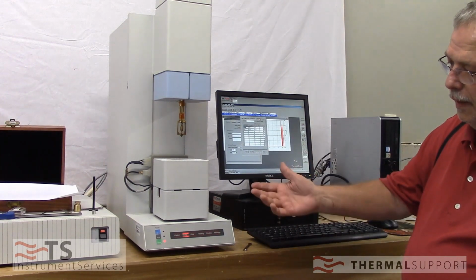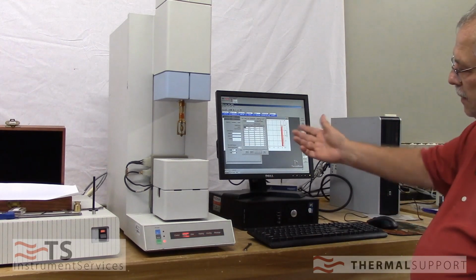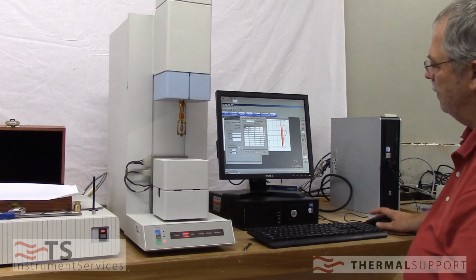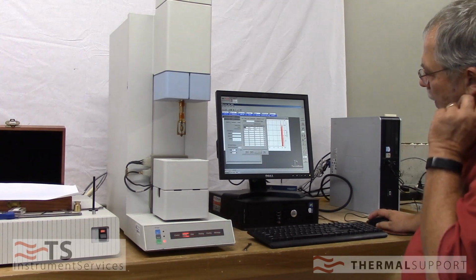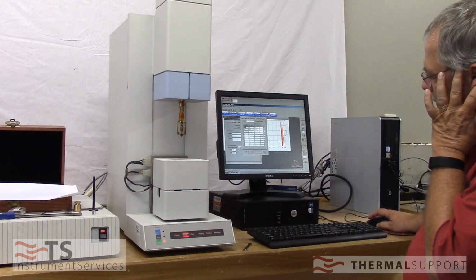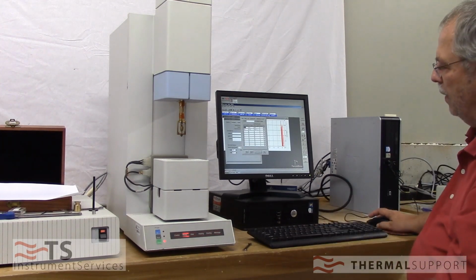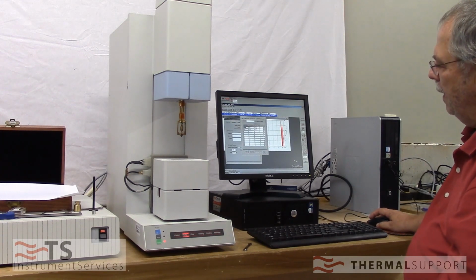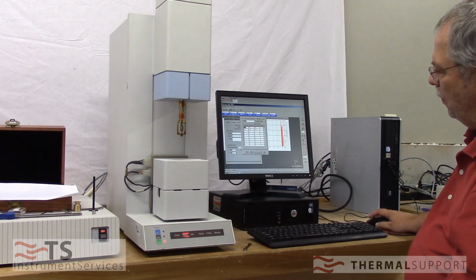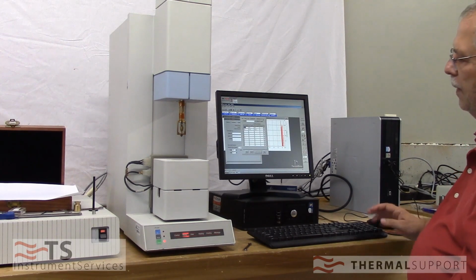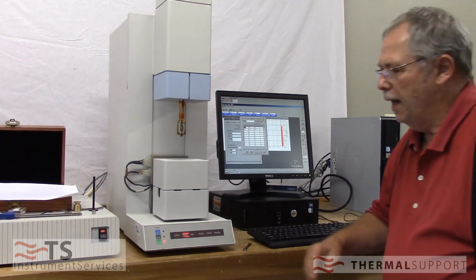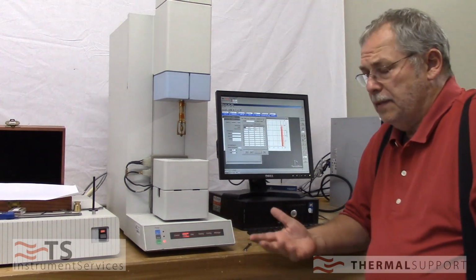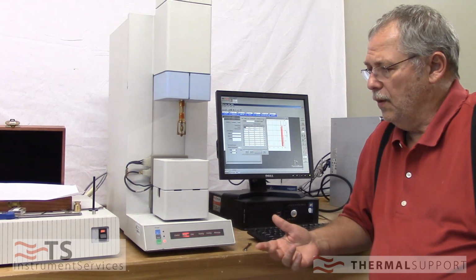we would put an indium in here. There are methods in here for DMA7, and we would run an indium, then we'd run a zinc, or we could run lead or whatever else we wanted to run, and then we would save and apply like before, and then we would go over here to the furnace calibration. And furnace calibration takes about 2 hours. You put the two temperature calibrations in there first. They take a little while.